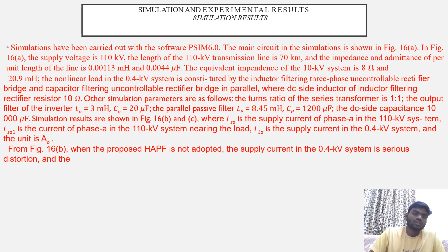In the experiment, the supply voltage is 0.4 kilovolts. With the nonlinear load, the distortion rate of supply current is 45%, and the distortion rate of supply voltage is 5.3% when the proposed HAPF is not adopted. When the proposed HAPF is put into use, the distortion rate of supply current is reduced to 2.9%, and the distortion rate of the supply voltage is reduced to 1.28%. So harmonic content of supply current and harmonic voltage are significantly reduced, waveforms of supply current and supply voltage are close to standard sine waves, and the harmonic resonance problem can also be suppressed.